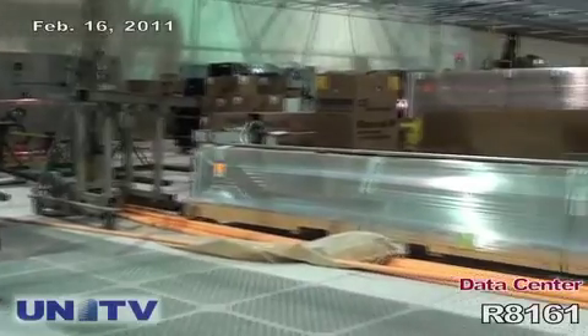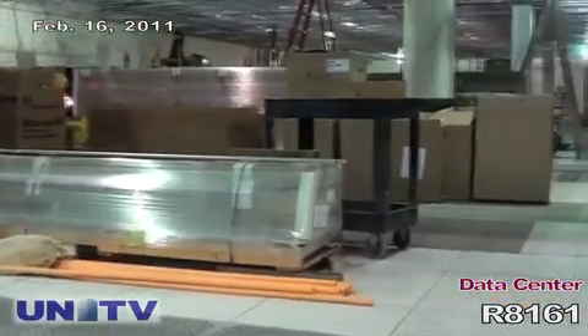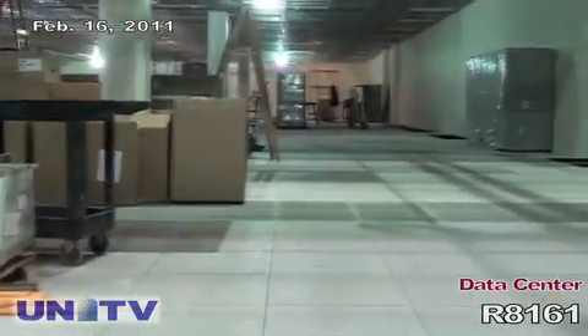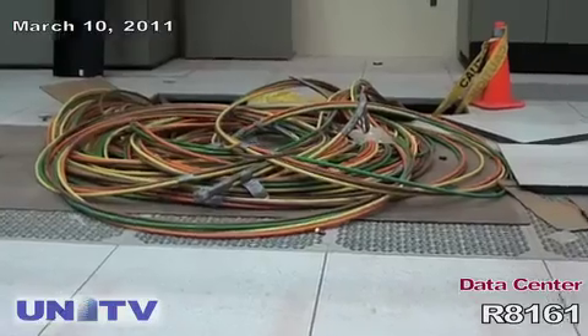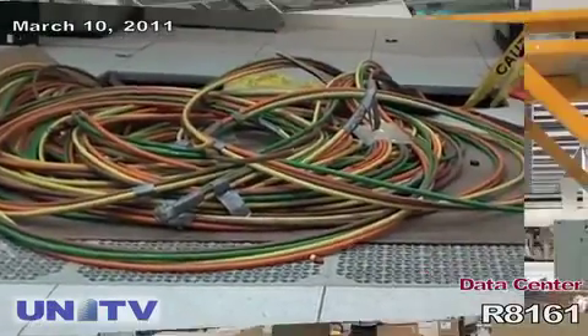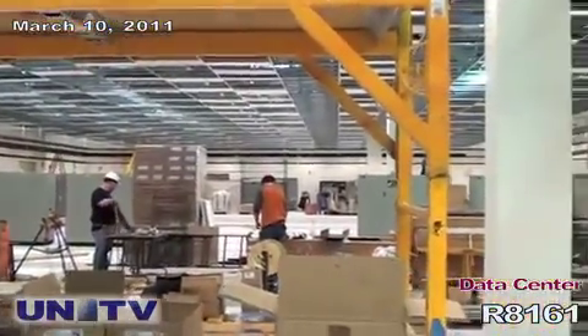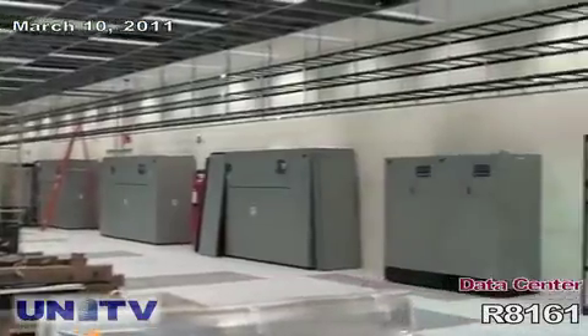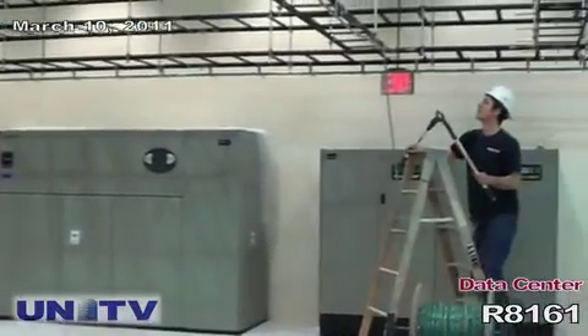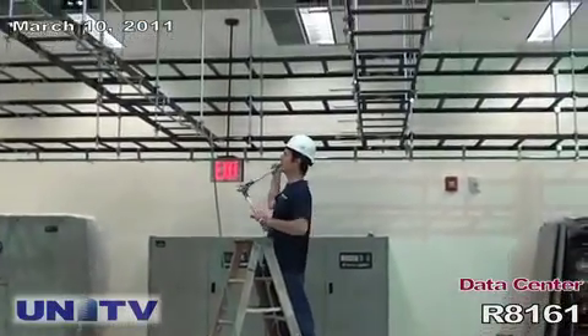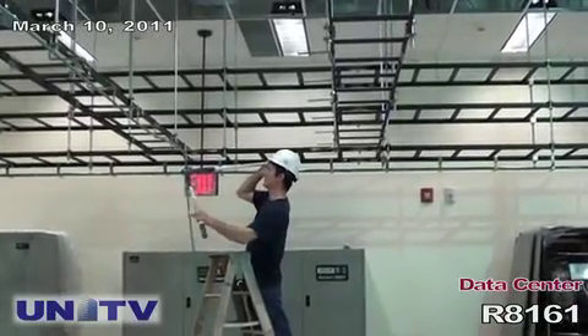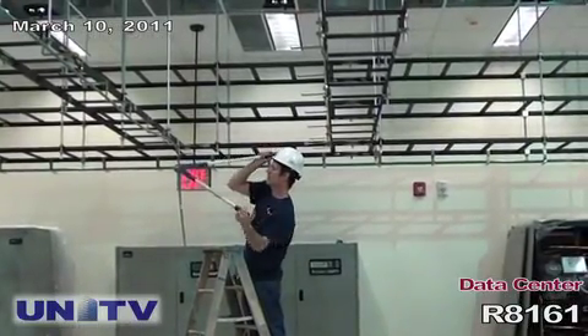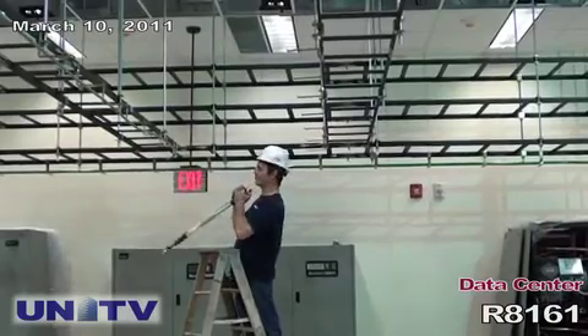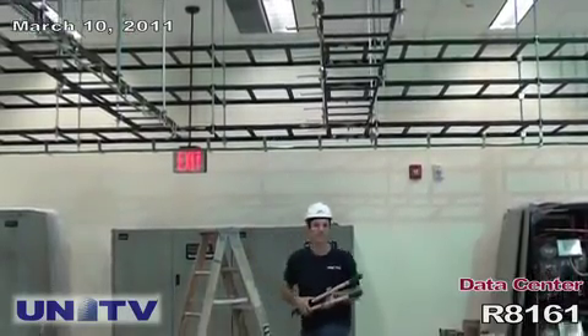This is a data center under construction. Those are CRAC units there. These are the PDU feeds. Ceiling grids up, ladder racks in, lighting's in. There's grounding associated with the ladder rack. We also install a Panduit in the ladder rack.